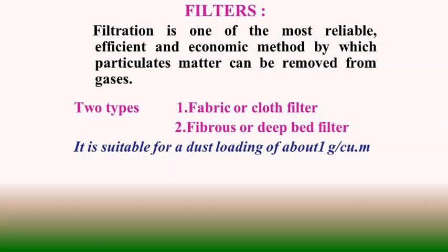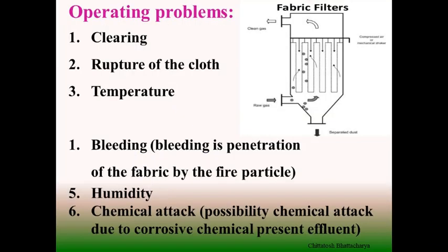Filters are another type of dust separating system. Filtration is one of the most reliable, efficient, and economic methods for separating particulate matters from dust-laden gas. There are two types: fabric or cloth filters, and fibrous or deep bed filters. Filters are suitable for a dust loading of about 1 gram per cubic meter; at higher loading it may affect filter performance. Major operating problems include clearing accumulated dust, rupture of cloths, burn-out at high temperature, bleeding — which is penetration of the fabric by fine particles — humidity changes, and possible chemical attack from corrosive chemicals in the effluent.